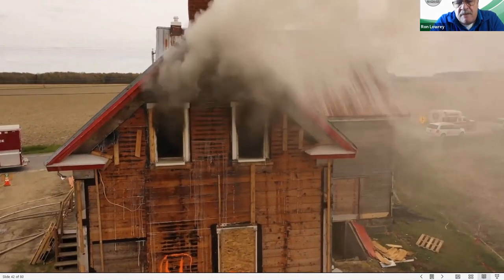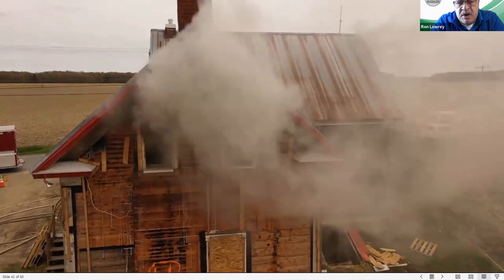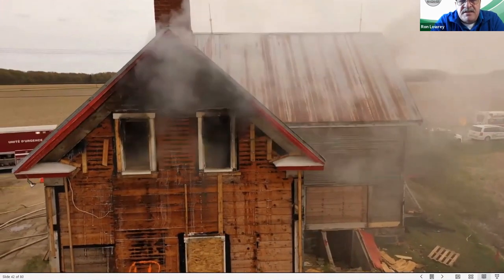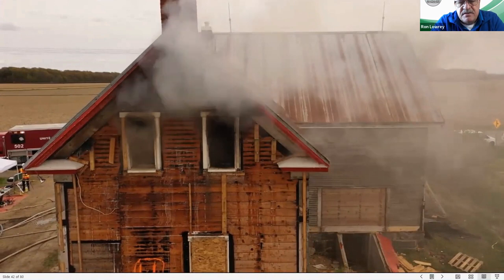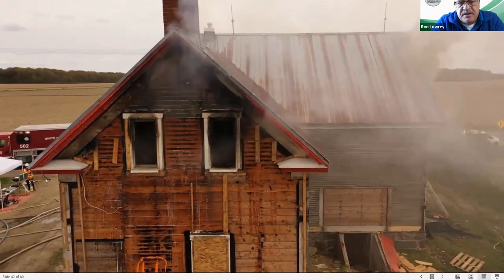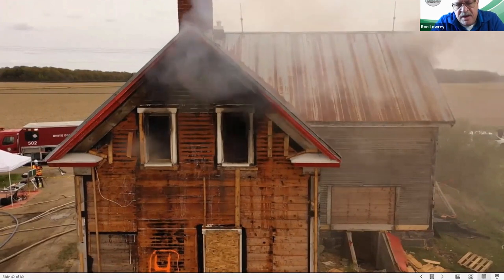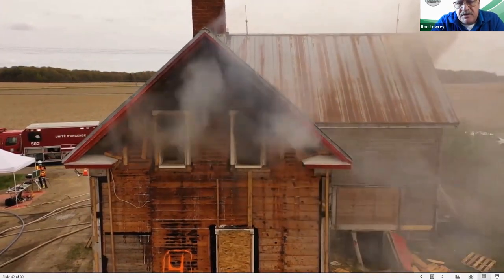We talk about stopping that formation of the smoke and the toxins in the smoke. The agent's continuing to do that. Even though it's not still being applied, it's actually improving those interior conditions. The fire's not extinguished. You're going to see it here over the course of probably the next minute as the fire is going to build back up. But look how rapidly the conditions have improved.